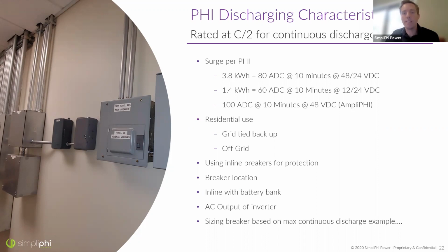Of course, these have to be DC rated breakers, right? So there's a difference between AC and DC rated breakers. And you also want to pay attention to the AC output of your inverter. So if your inverter is a 10 kilowatt inverter, you should be able to figure out how many batteries you need to continuously deliver 10 kilowatts.